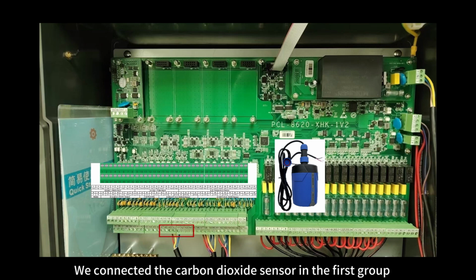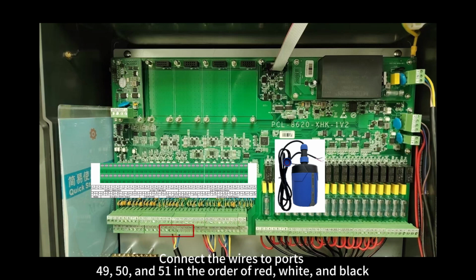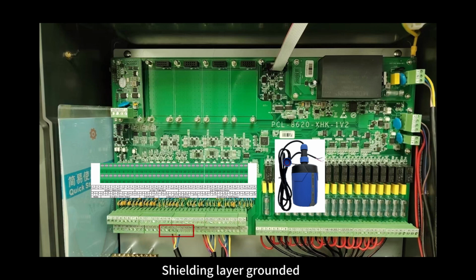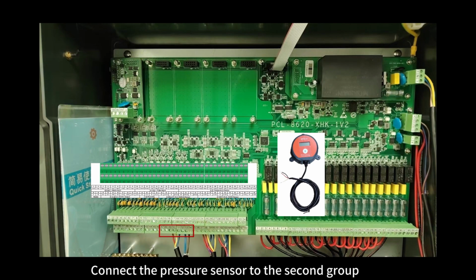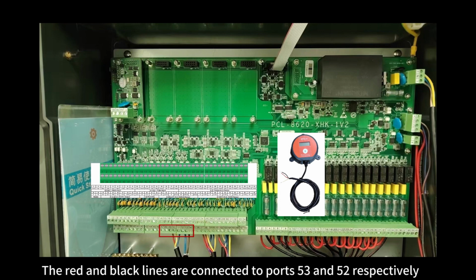We connected the carbon dioxide sensor in the first group. Connect the wires to ports 49, 50, and 51 in the order of red, white, and black. Shielding layer grounded. Connect the pressure sensor to the second group. The red and black lines are connected to ports 53 and 52, respectively.